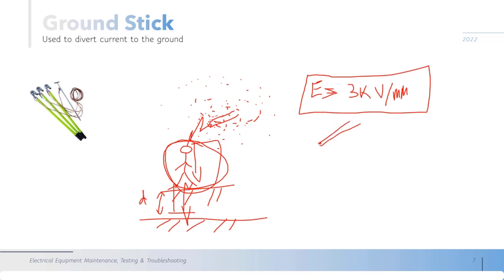Let's see the application. You have the wire here and you are far away from the line and you respect the minimum distance. This is the electric field and you respect this distance. So with this ground stick, as I said, it is insulated from this side to this side, so this part is also insulated better than the air. You touch the line with this surface, and there is a wire that will be connected to the ground before you connect here, and you will discharge all the remaining voltage to the ground.